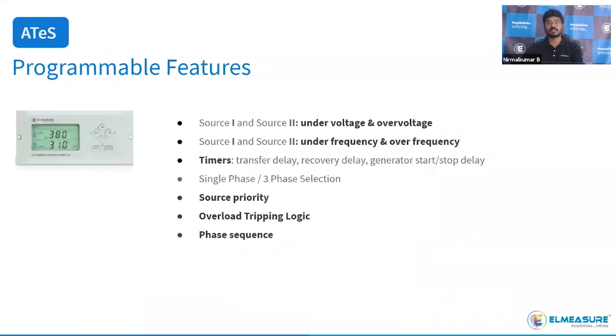Programmable features via remote display include: source one and source two under-voltage and over-voltage, frequency protection, timers such as transfer delay, recovery delay, generator start and stop delay, source priority, overload tripping logic, and phase-sequence enable/disable options.